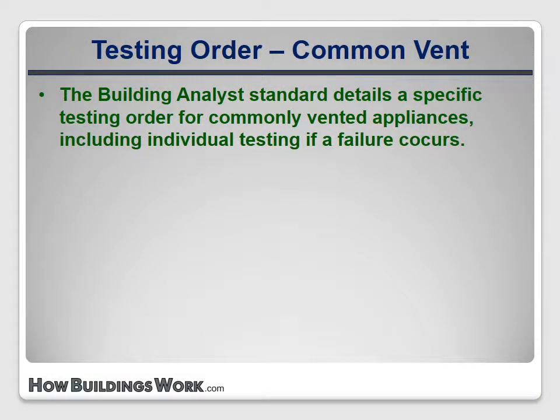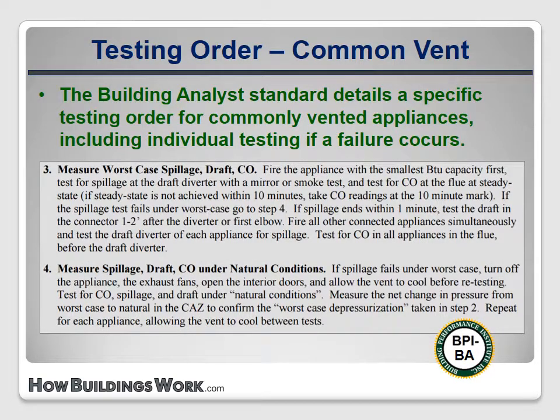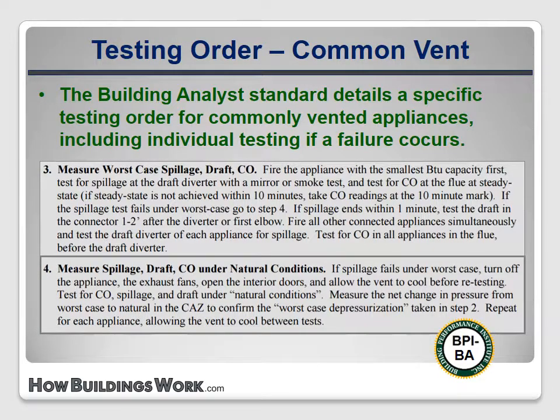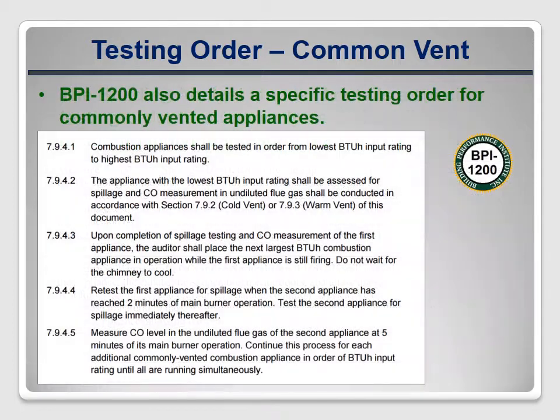The Building Analyst Standard details a specific testing order when multiple appliances share a vent: the smallest appliance should be tested first, then others in order of BTU rating leaving smaller appliances running. If any appliance fails, all should be retested alone under natural conditions, allowing the flue to cool between tests. BPI 1200 states that all appliances should be fired in order of increasing BTU per hour input capacity, and that larger appliances should be tested with all smaller appliances operating simultaneously. There is no requirement to ever test the appliances independently, even if a failure occurs.